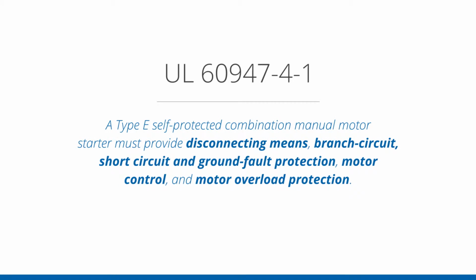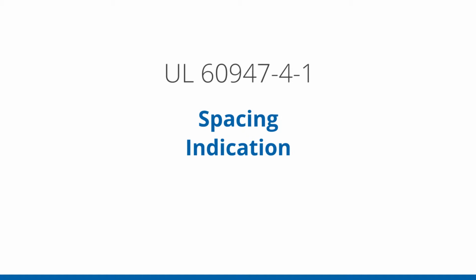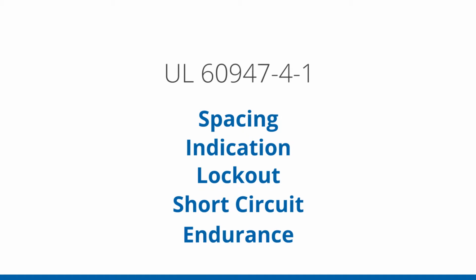As defined in UL 60947-4-1, the Type E self-protected combination manual motor starter must provide disconnecting means, branch circuit, short circuit and ground fault protection, motor control, and motor overload protection. There are specific requirements by UL for spacing, indication, lockout, short circuit, and endurance for a Type E combination self-protected motor starter. How do we utilize the motor protection circuit breaker as a Type E self-protected combination manual motor controller?